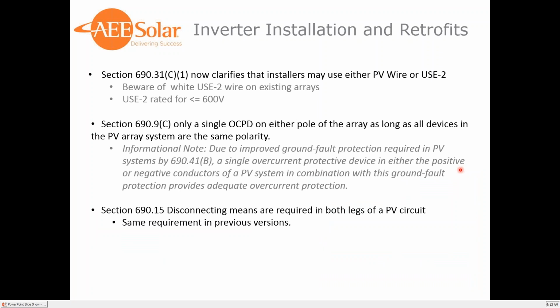Inverter installation and retrofits. So section 690.31(C)(1) now clarifies that installers may use either PV wire or USE-2. One thing to be aware of is white USE-2 on existing arrays if you're going to do a retrofit for an existing inverter that's on there. If you do a retrofit and you're actually pulling a permit to do that, you actually won't be code compliant if there is white USE-2 as the negative conductor.